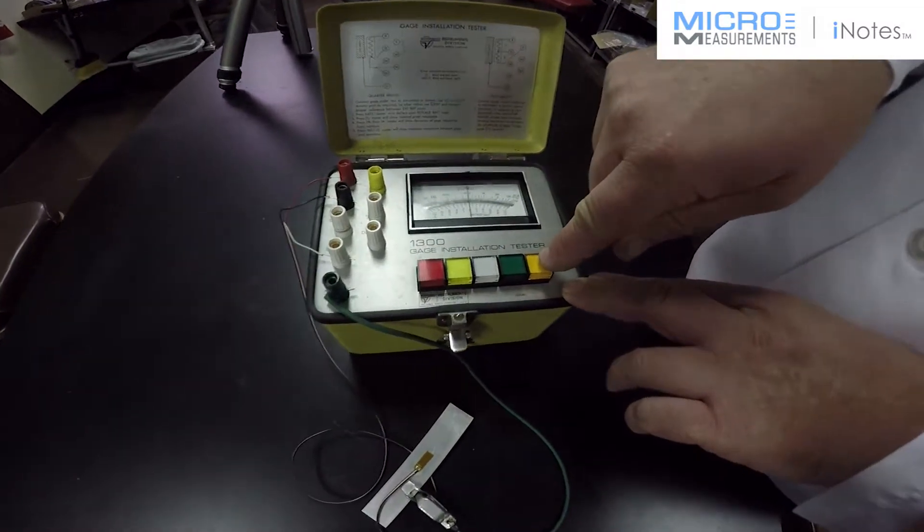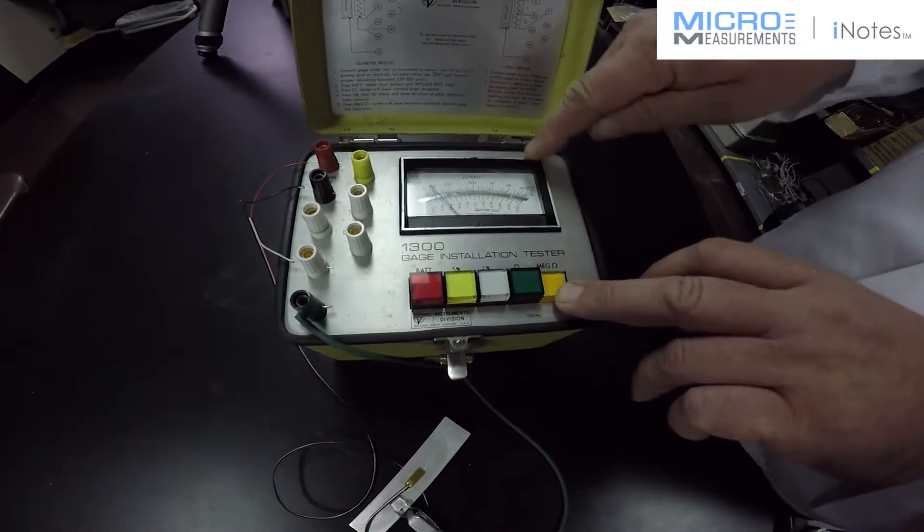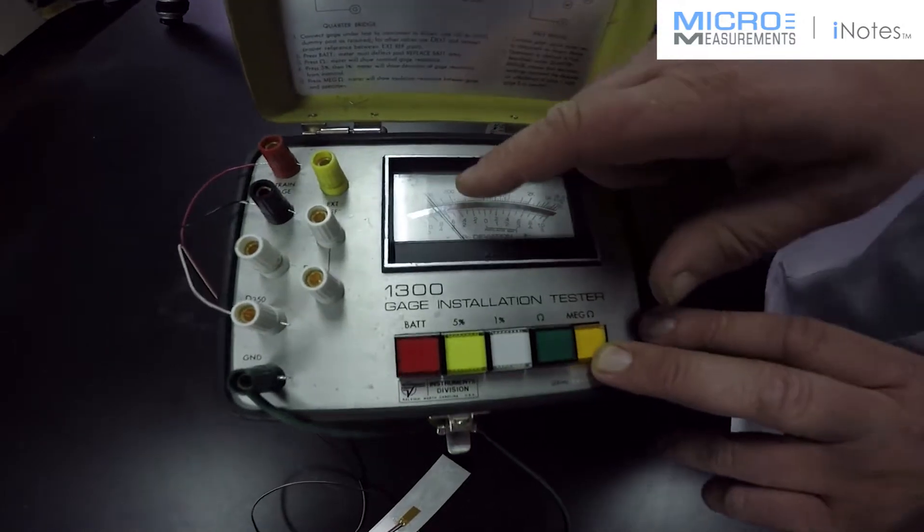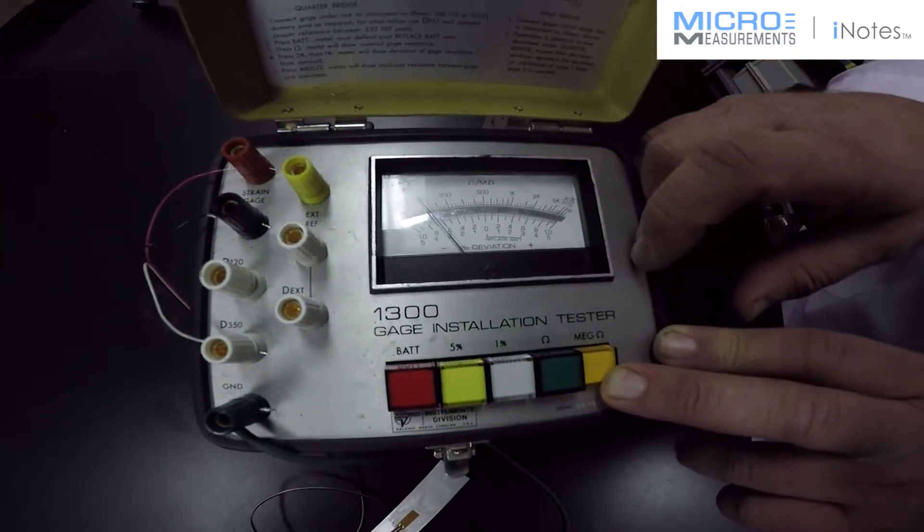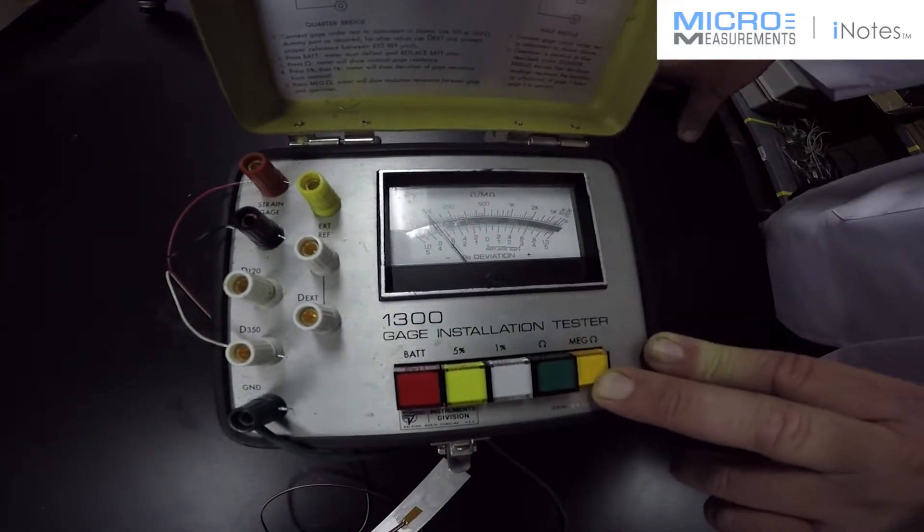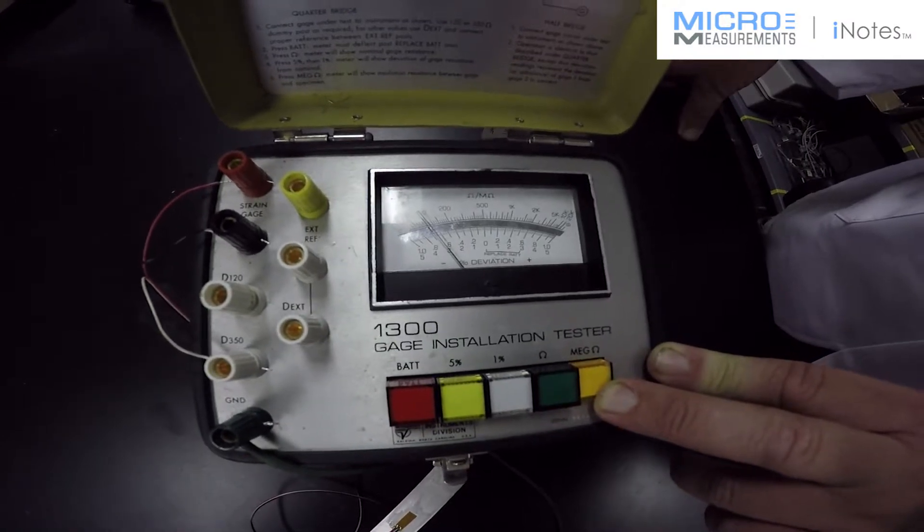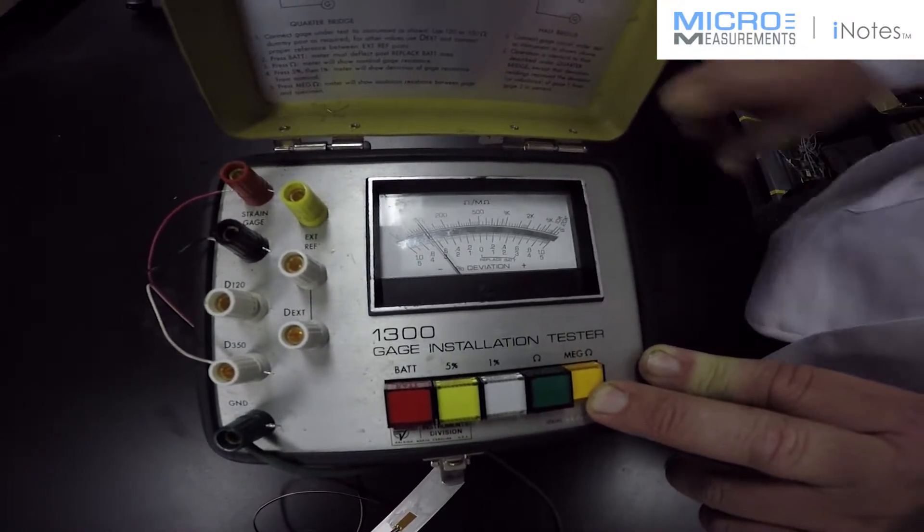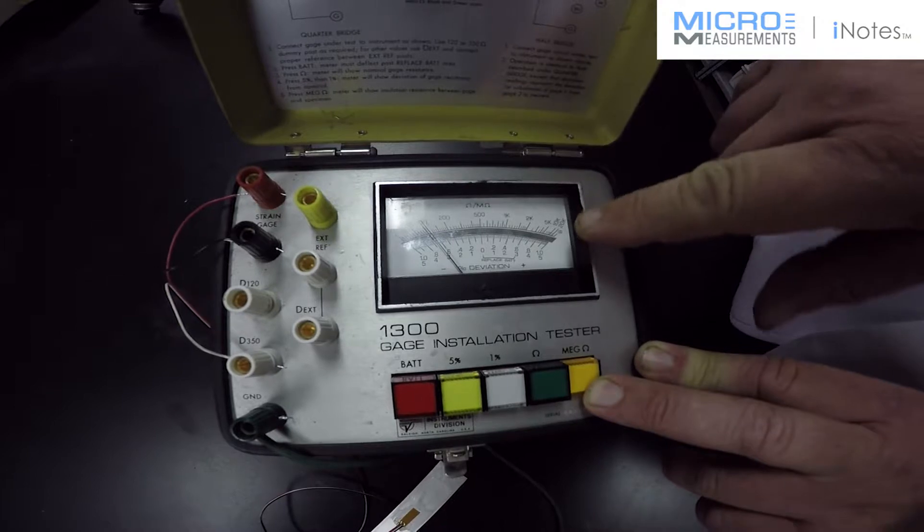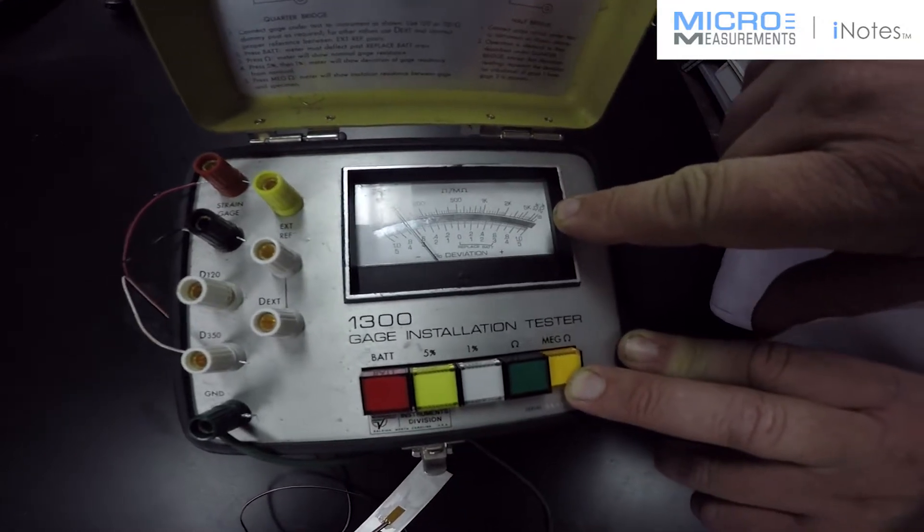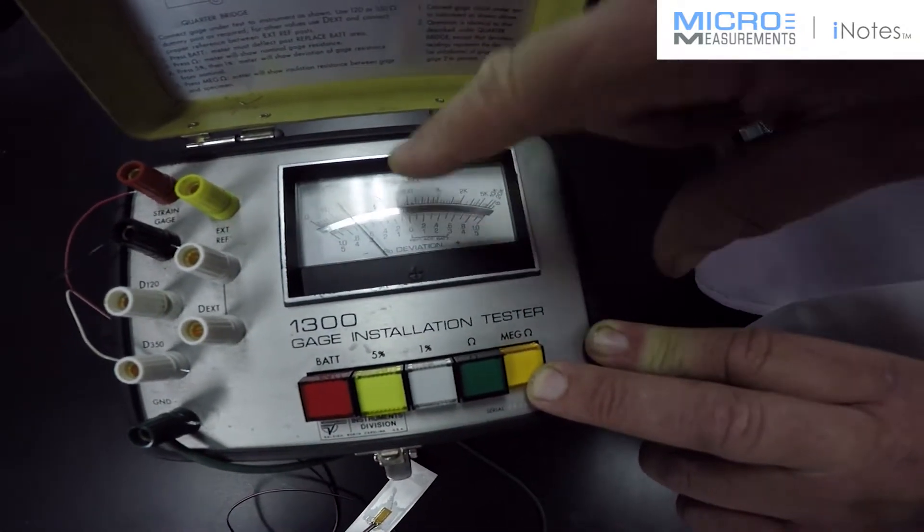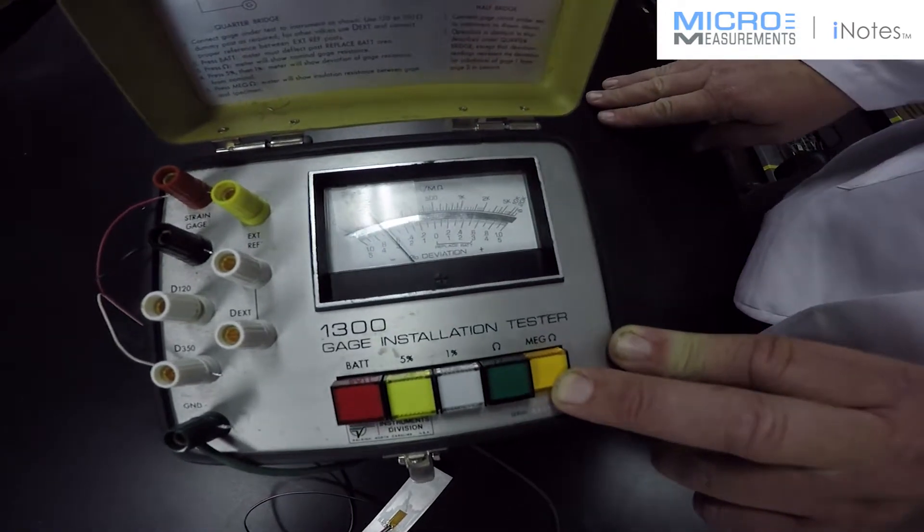So I'm going to press the mega ohm button. And on the top scale, I can see that right now it's reading about 100 mega ohms. That's too low. What you want to see with the strain gauge is up here on this end, about 10k mega ohms. It's kind of like the go or no go. If it's less than that, I've got problems I want to fix.